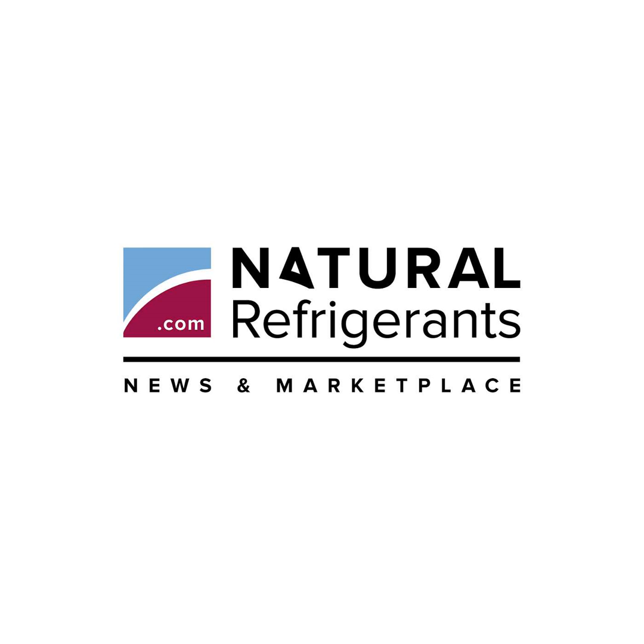Mitsubishi Electric revealed its upcoming EcoDan CAHVZR 290 commercial air source heat pump, launching globally in summer 2026. The modular 40 kilowatt units can be cascaded up to 280 kilowatts and deliver up to 75 degrees Celsius, 167 degrees Fahrenheit, outlet temperatures and ambient conditions down to minus 15 degrees Celsius, 5 degrees Fahrenheit. The heat pump can provide cooling in addition to heating and hot water.